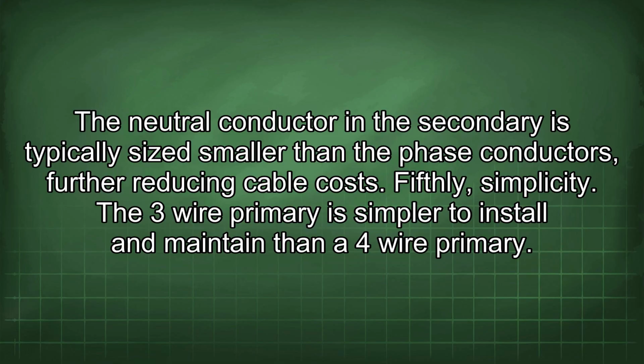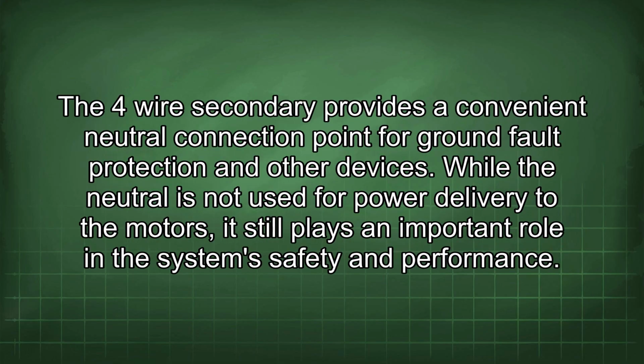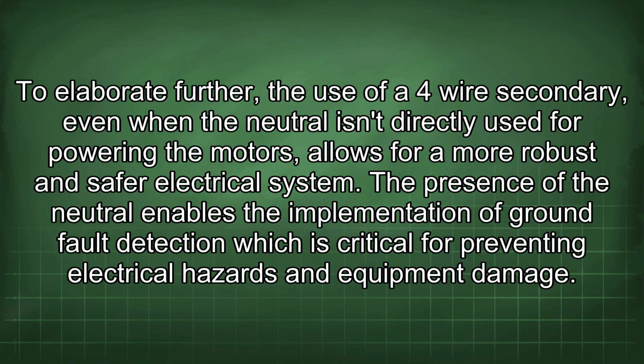Fifthly, simplicity. The 3-wire primary is simpler to install and maintain than a 4-wire primary. The 4-wire secondary provides a convenient neutral connection point for ground fault protection and other devices. While the neutral is not used for power delivery to the motors, it still plays an important role in the system's safety and performance.